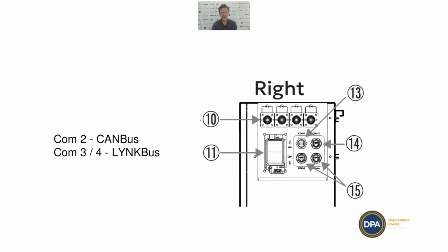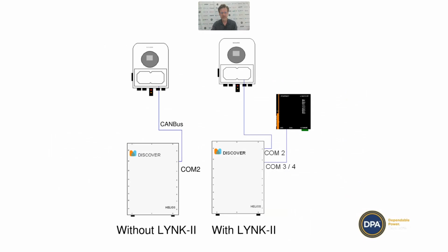So we went over this before as well. The CAN bus output is on COM2, which is number 14 here. There's two different, it can be a bit confusing with closed loop communication with Discover products. So the original rack mount batteries, if you're familiar with those, did not have CAN bus output on them. They connected to the LYNK II device, one of these, and the LYNK II had the CAN bus output. The Helios batteries have CAN bus built into them, so you don't need a LYNK II at all. You can just go out of COM2 straight to the inverter.